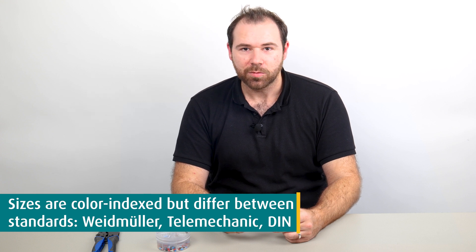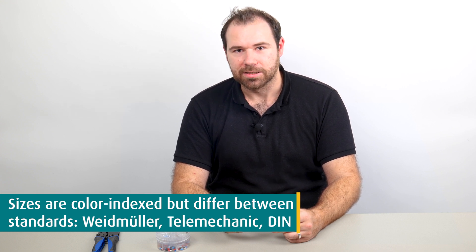Unfortunately, there are three common standards with a different color set each: Weidmüller, Telemechanik and DIN. So always pay attention to the applying standard if you are looking for a specific size based on the color. For the cable we are using here, a DIN black colored one with a cross section of 1.5mm² is the correct choice.